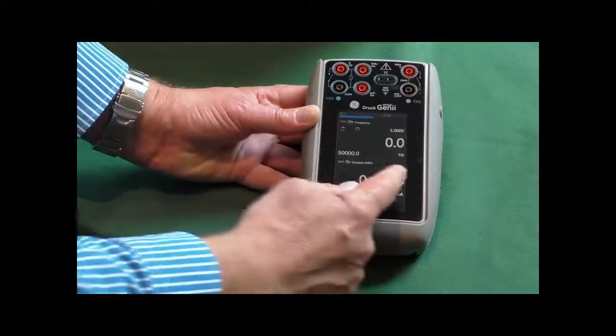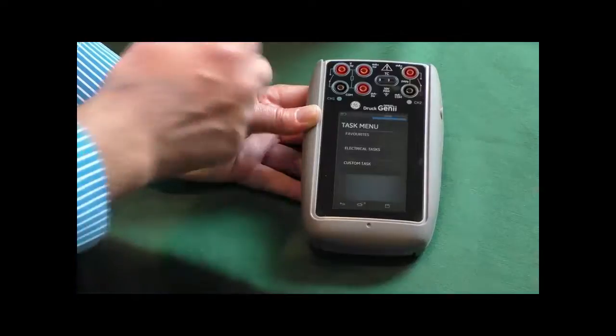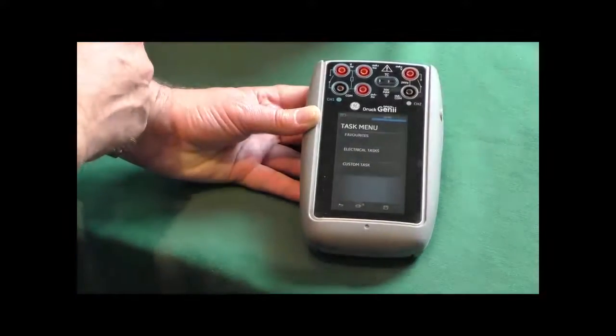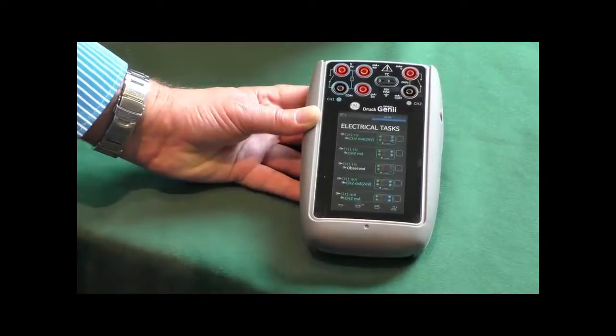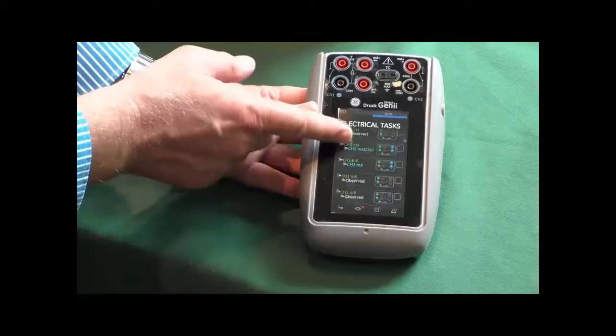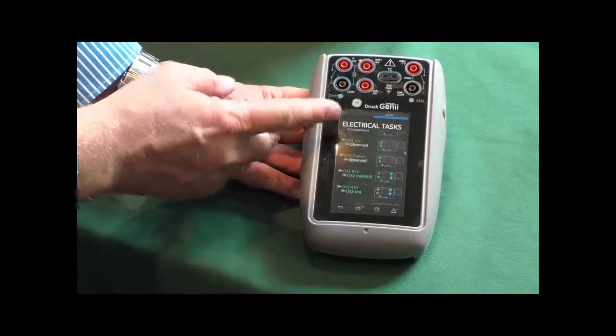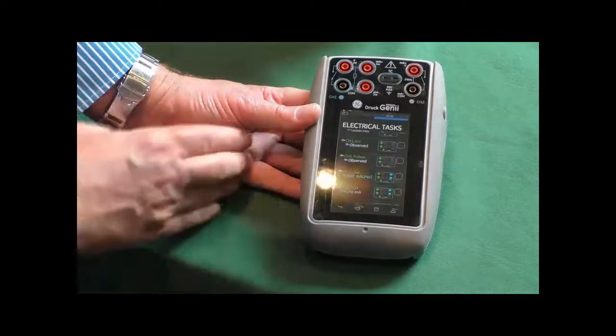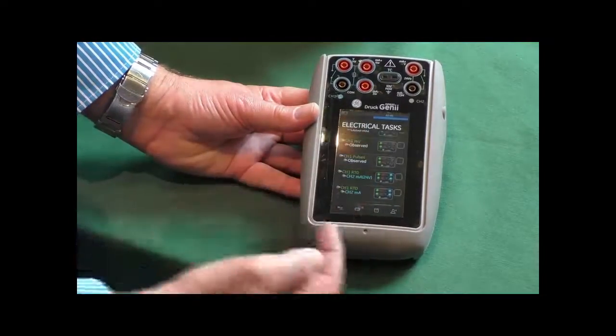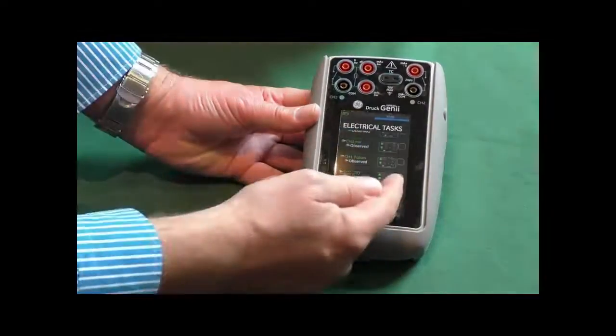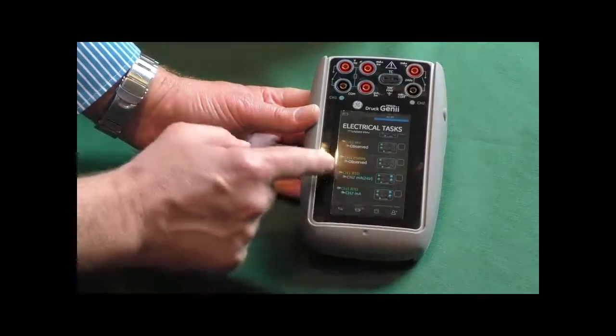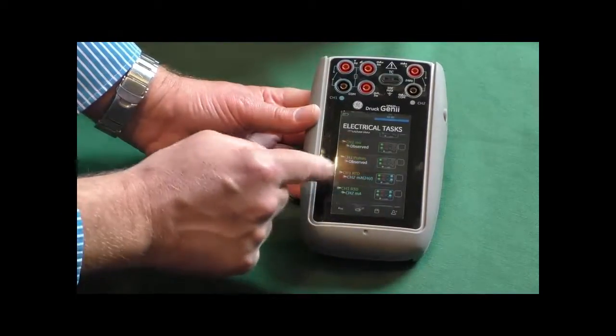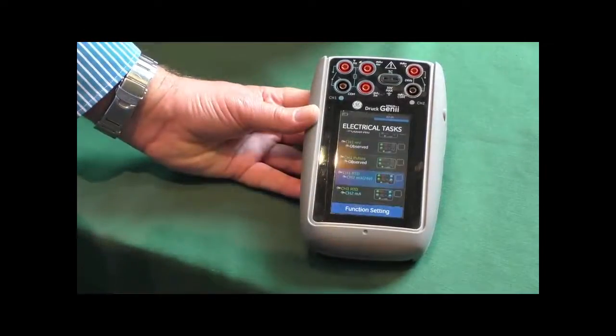I can actually go into this manually and do what we call a custom task and set that up for each one individually. But we also have our electrical tasks set up in here to make that a lot easier for us. And if we scroll down, what I'm looking for here is channel 1, I want an RTD, and channel 2, I want milliamps and 24 volts. The other good thing on the graphic, it shows me where I need to connect to on these two channels. So quite simply now, I will select channel 1, RTD, and channel 2, 24 volts and milliamps. So we'll just select that.